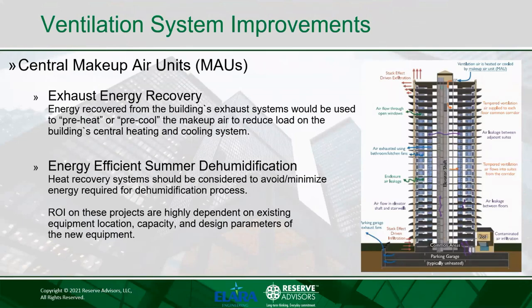So the next item would be ventilation system improvements. In high-rise residential buildings, exhaust is provided by central kitchen, dryer, and toilet exhaust fans, while fresh air is provided by a central makeup air unit. So when we think about ventilation systems in high-rise residential buildings, we need to think about exhaust and makeup air units. The exhaust air from residential kitchens, bathrooms, and dryers is typically replaced with conditioned, filtered outdoor air provided by central makeup air units.